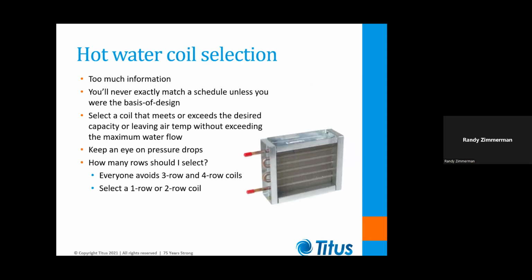Now for hot water coils, lots of people have trouble selecting coils because they can't get an exact match to the schedule they've been handed. And usually it's impossible to get an exact match unless you are the basis of design. Basically the key here is to try to select a coil that meets or exceeds the desired capacity or leaving air temperature without exceeding the maximum water flow by too much. And then just keep an eye on the water pressure drops. Now, most people are going to try to avoid 3 and 4 row coils. So usually the question comes down to, do I need a 1 row coil or do I need a 2 row coil?